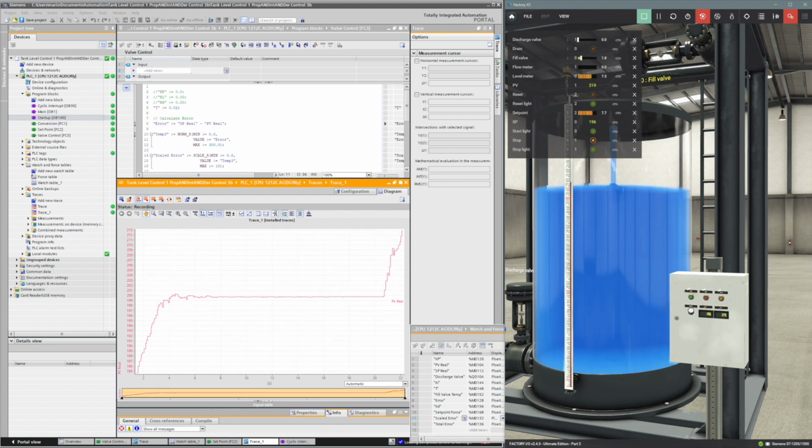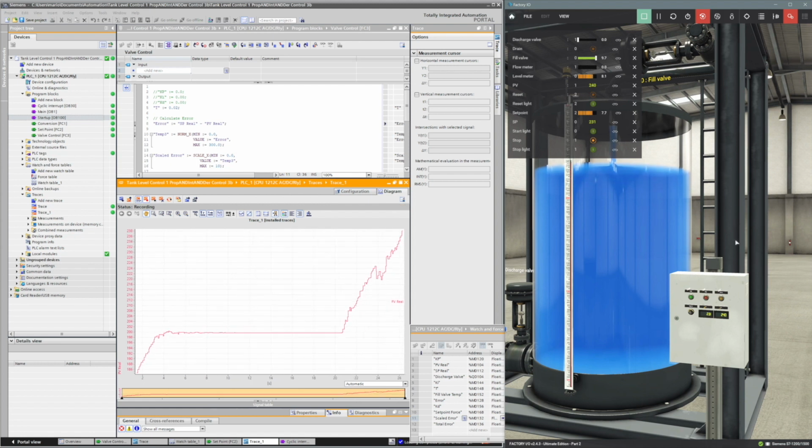Of course, we could do more tuning to improve the situation, but I'm not sure we can better it much more if using a derivative. With no disturbance, we again get an overshoot, so let's increase the set point and see what happens. Oops, I increased it, then reduced it again. No problem. I'll increase it. Again, a bit choppy or turbulent.